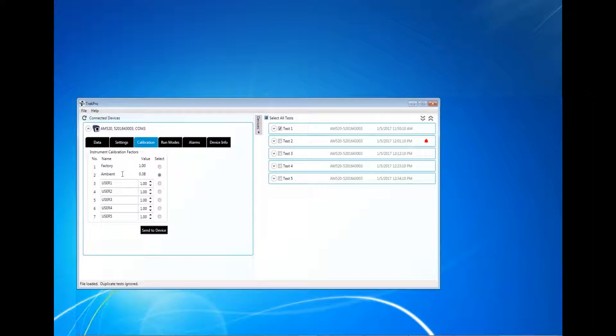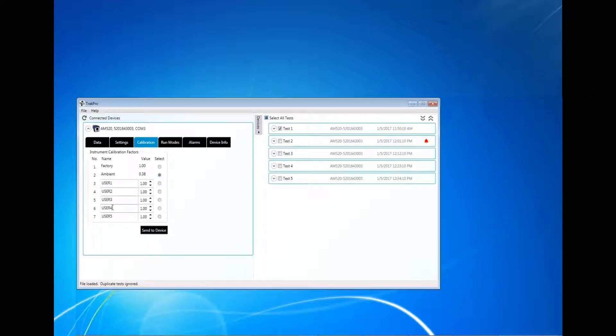User CALS 3 through 7 can be renamed, configured, and sent to the device. The actual values for user CALS 3 through 7 can also be changed using the AM520 menu system and keypad.